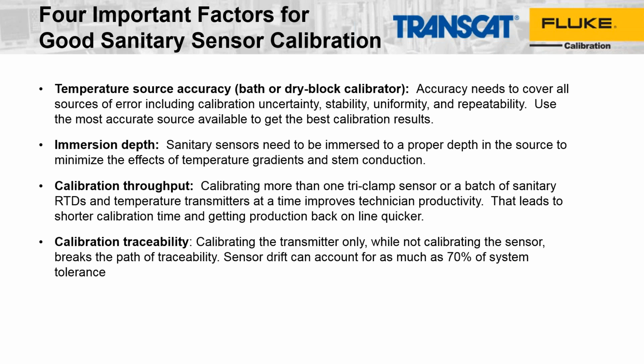For example, one reason why this can be an issue is because in some applications the technicians are only calibrating the transmitter, and they consider the sensor doesn't need to be calibrated, or the sensor is some kind of intrinsic standard that doesn't need recalibration. But the reality is the sensor drift alone can cause as much as 70% of the error budget, or the specification for the transmitter and temperature probe system.